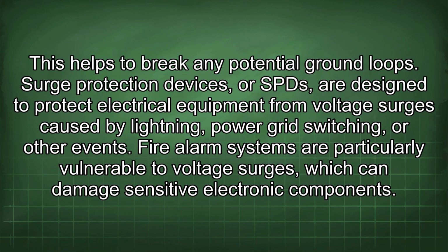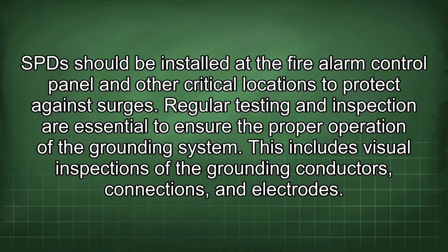Surge protection devices, or SPDs, are designed to protect electrical equipment from voltage surges caused by lightning, power grid switching, or other events. Fire alarm systems are particularly vulnerable to voltage surges, which can damage sensitive electronic components. SPDs should be installed at the fire alarm control panel and other critical locations to protect against surges. Regular testing and inspection are essential to ensure the proper operation of the grounding system. This includes visual inspections of the grounding conductors, connections, and electrodes.